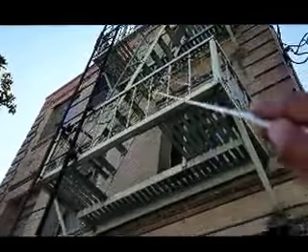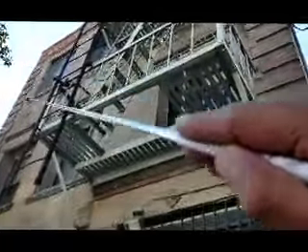Refurbishment. As you can see, the fireman's ladder, I made my way towards the roof. Now I made my way down. Some of the items you could tell from the bottom portion: original hardware, original square head bolts and rivets, anywhere from 50 to 75 and 75 to 100 years old. Those are recommended to be swapped out and rebolted with new hardware, which is hex head bolts.